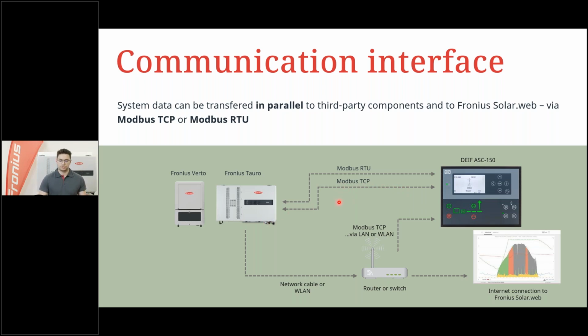If you do it with the Modbus TCP connection and via Ethernet cable, for example, you can go to a router or a switch directly, and therefore you have 2 things possible. One is the control and the connection to DEIF, and in parallel, you can also go to Fronius Solar.web and use the monitoring platform of ours. So if you go for Modbus TCP, both is possible, no worries. And this goes for the Fronius Verto and the Fronius Tauro, as we have here the new Pilot card, the new communication card integrated.